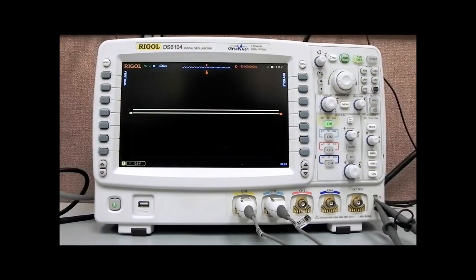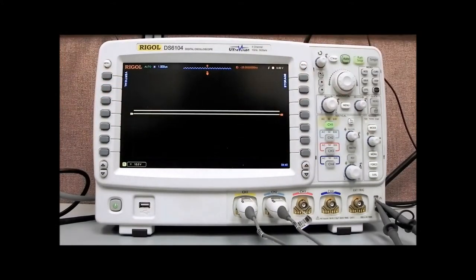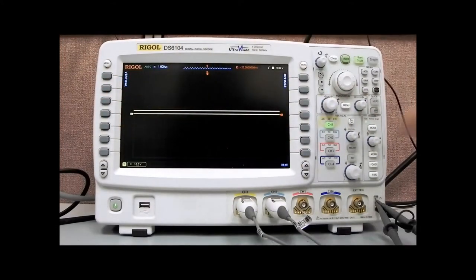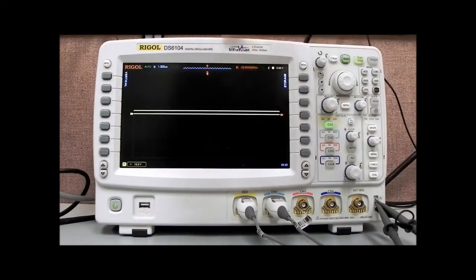We could describe the display. This would be the entire memory location, and what we're seeing on the display is a small window of that. As we take that window, we can move it through time along the waveform. You can imagine the waveform, if we had an infinite display on either side, would continue on, and we would be able to move that window back and forth, both horizontally and vertically.